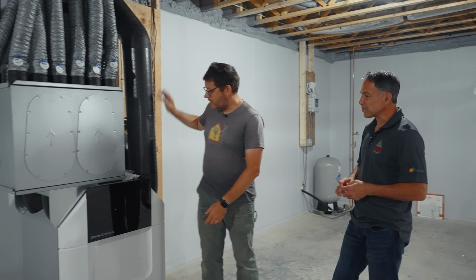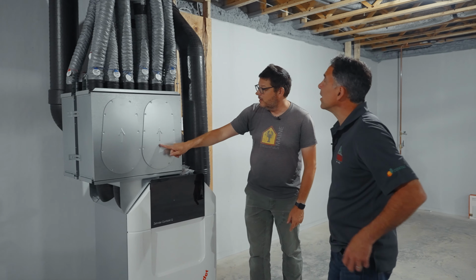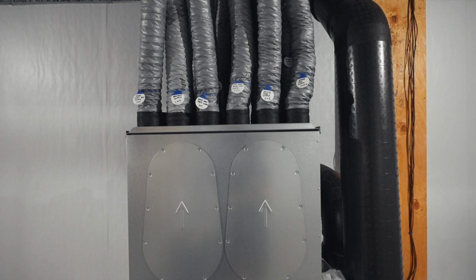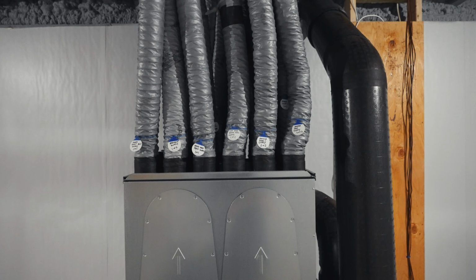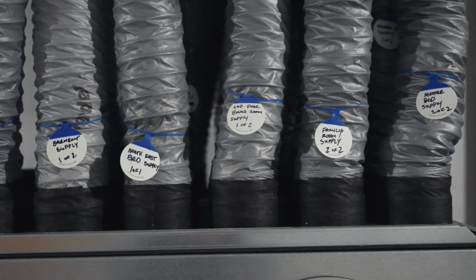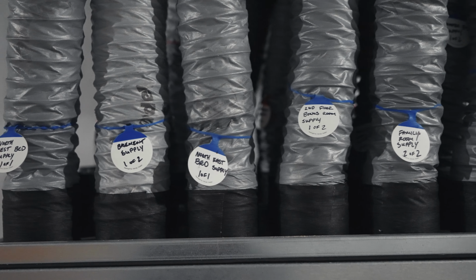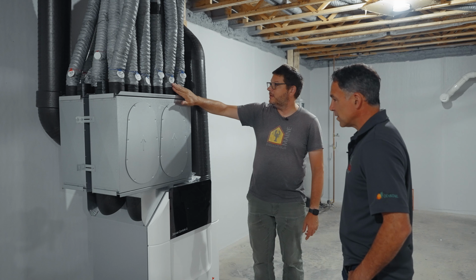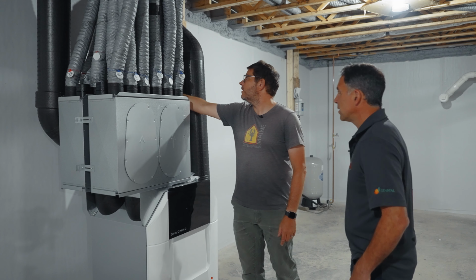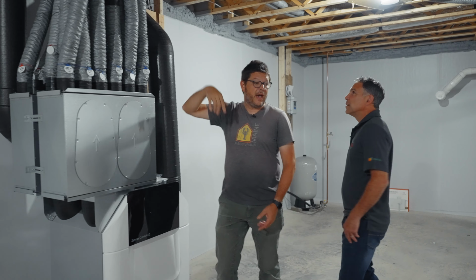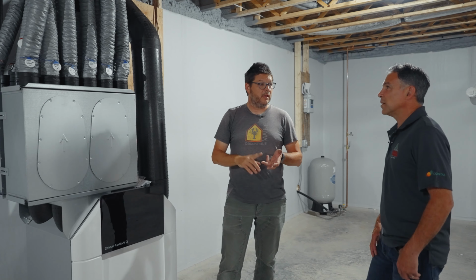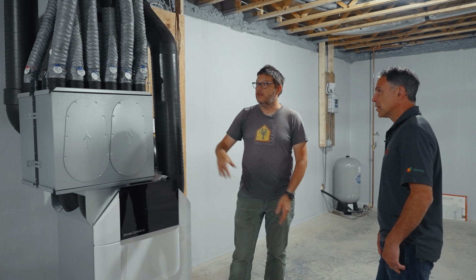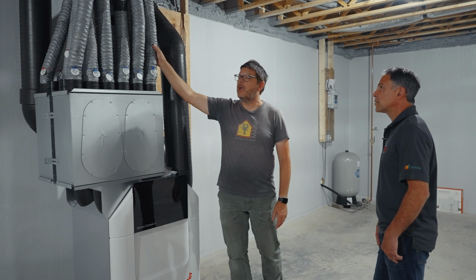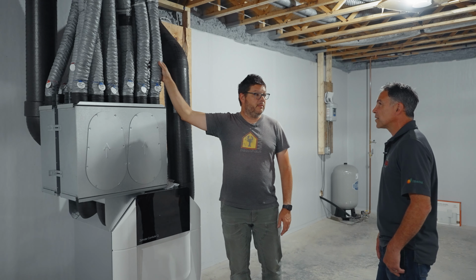With this system, fresh air is coming in, going through here. See the arrows going up? These are all identifying the rooms they're going to. These 9 tubes here are all going to bedrooms and living spaces, so this is the fresh air coming in. The other box in the back has red tags, coming out of the kitchen, the bathrooms, and the laundry exhaust room. Each one of these tubes is designed to carry approximately 12 CFM of air.